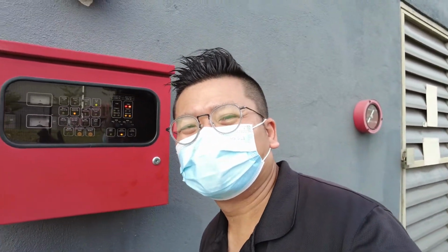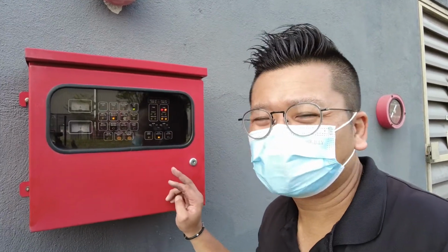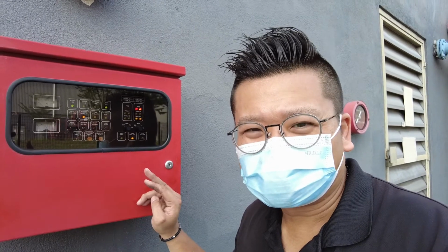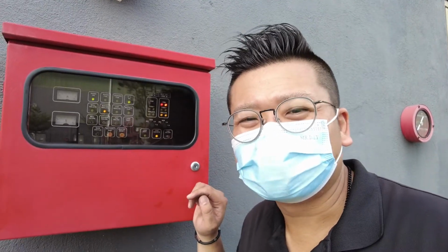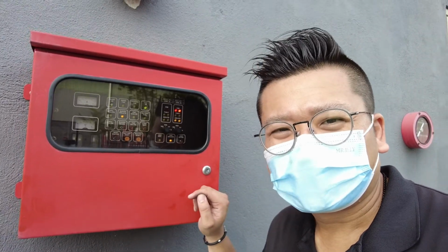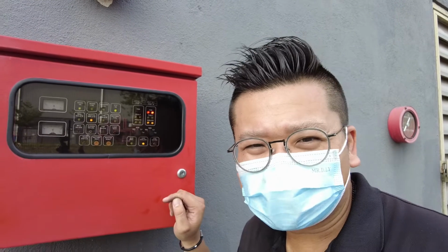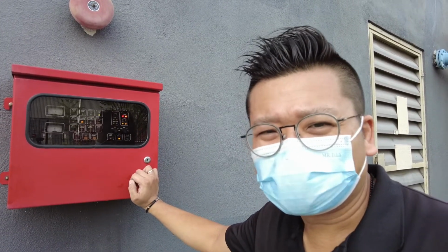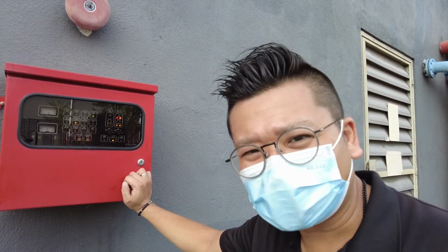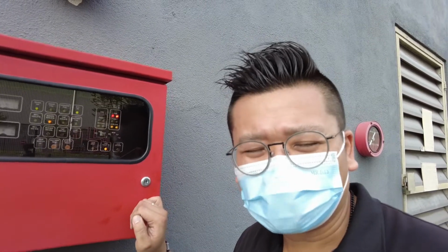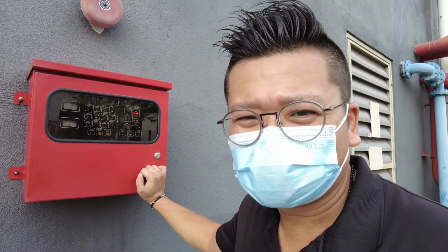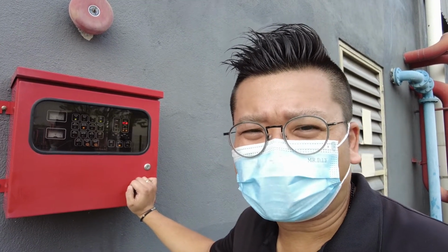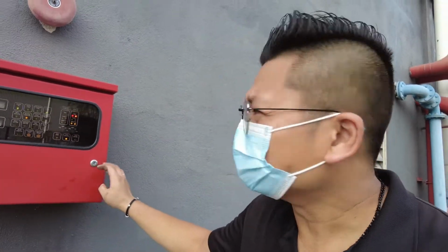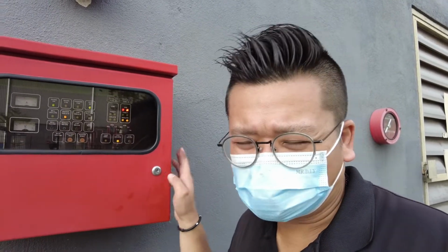Before you enter an HV room or LV room, you will always encounter the CO2 panel. Always check the CO2 panel. Is it triggered, normal, or is there any alarm signal? By regulations, whenever you enter the HV room, LV room, or Genset room, where there's a CO2 extinguishing system inside, you need to isolate the tripping first. This is for safety. Because once you are inside, if there's any triggering or mis-triggering of the CO2 system, and you are alone inside and nobody knows, and you faint inside, or you are trapped inside and not able to come out, as the CO2 system discharges, it will cause you to be unable to breathe. 5 minutes without oxygen to the brain is death. So it is very important to know how to maintain this CO2 fire extinguishing system.